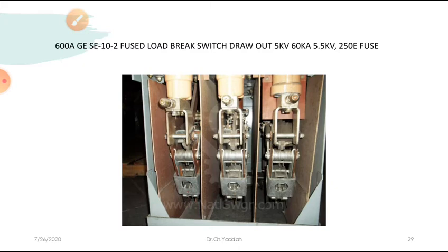For example, for an 11 kV feeder carrying some current, once you suddenly chop it, the voltage built up between the two contacts may be several times 11 kV. That high voltage easily ionizes the very small air gap between the two contacts.